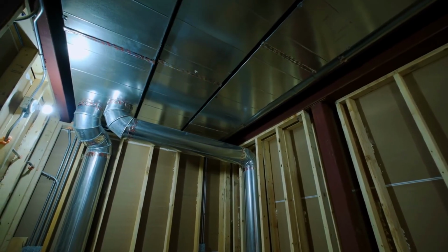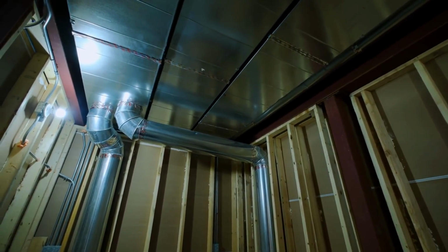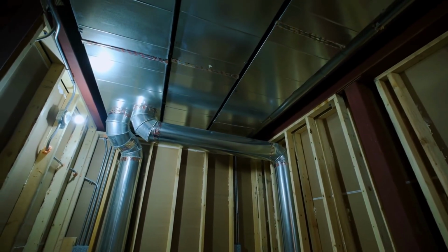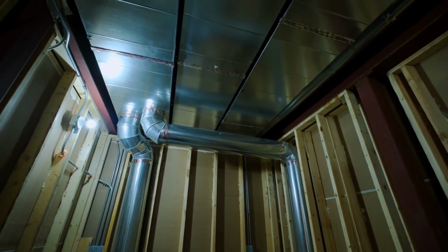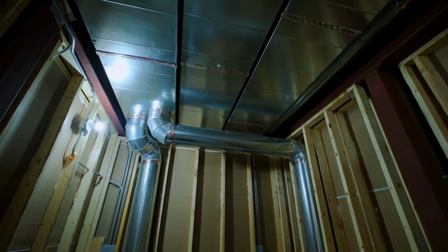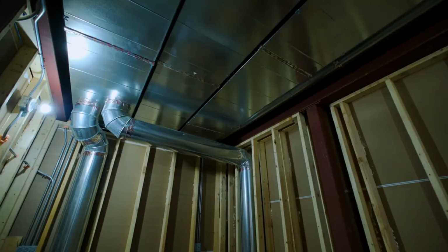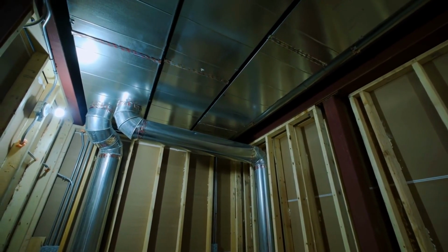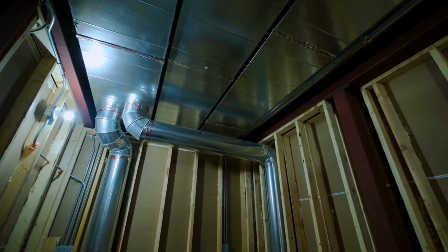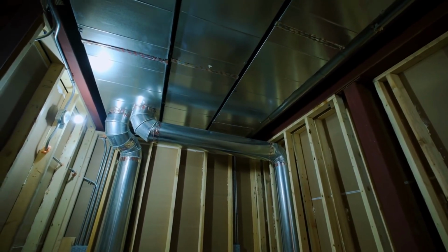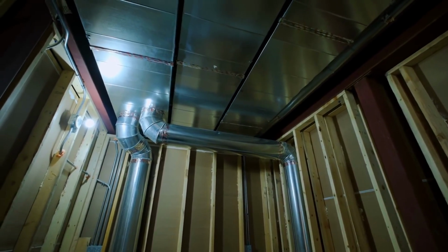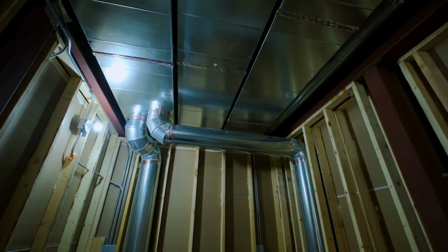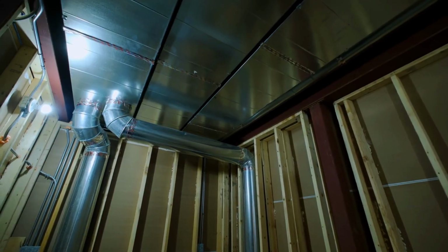6.2.7. The design requirements for corridors HVAC unit according to SCA HVAC for new construction and major modifications. In new construction and major modification projects with adequate ceiling heights, corridors should be served by either 1. Custom multi-zone classroom variable air volume heat pump units, or 2. Classroom dual-temperature multi-zone VAV air handling units that are served by air-to-water heat pump chiller heater systems. The use of these systems is subject to SCA review and approval during the early design phases.